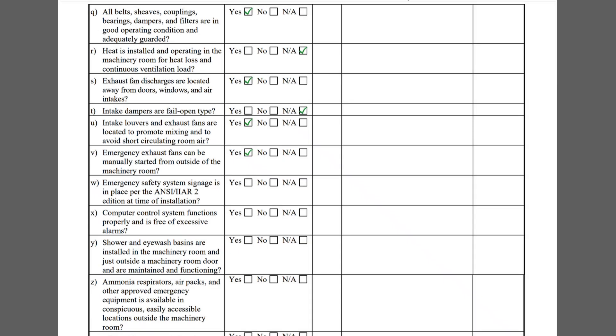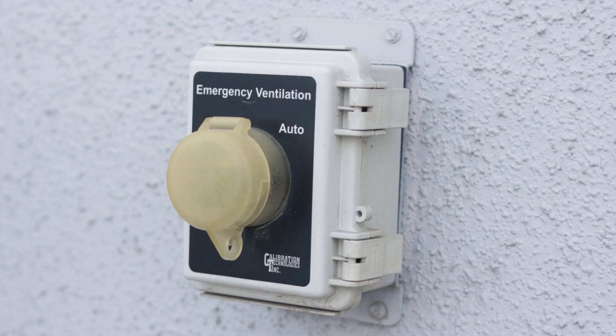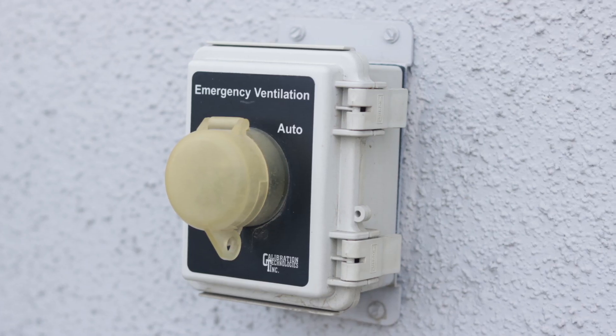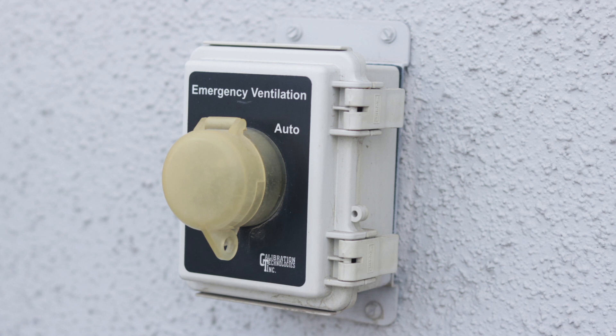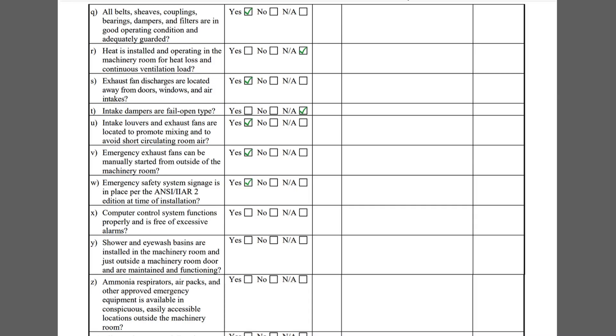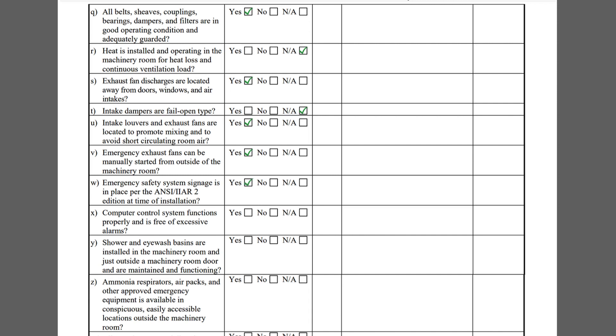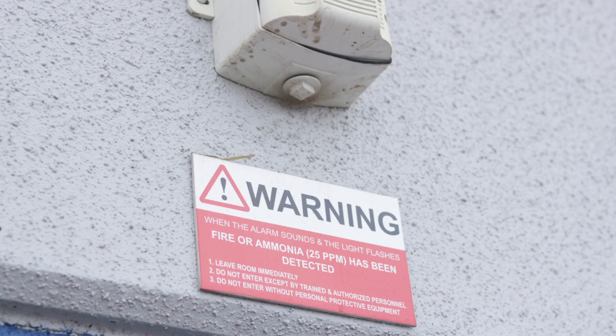Emergency exhaust fans must be able to be manually started from outside the machinery room per Item V. This switch next to the door provides that capability. Checklist Item W asks if emergency safety system signage is in place per the ANSI IIAR 2 edition at the time of installation. The signage at this facility is exceptional.